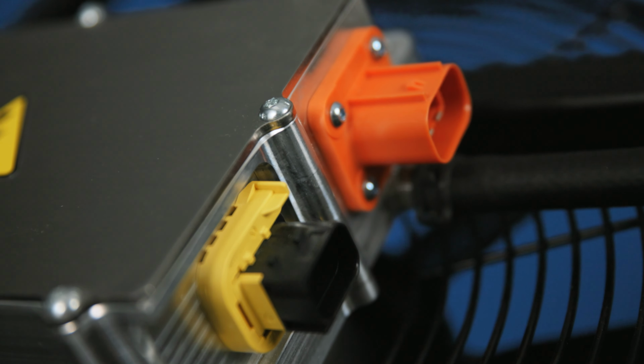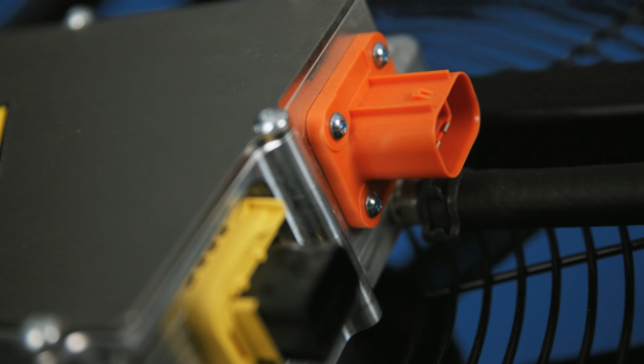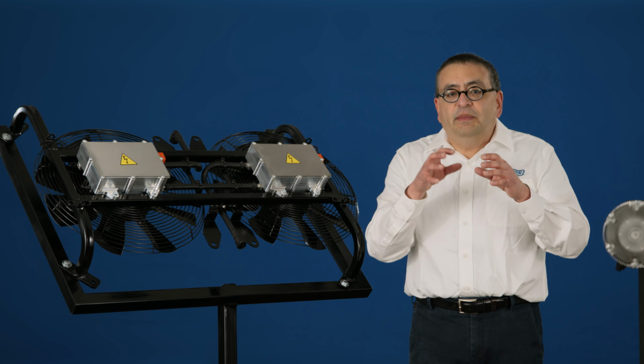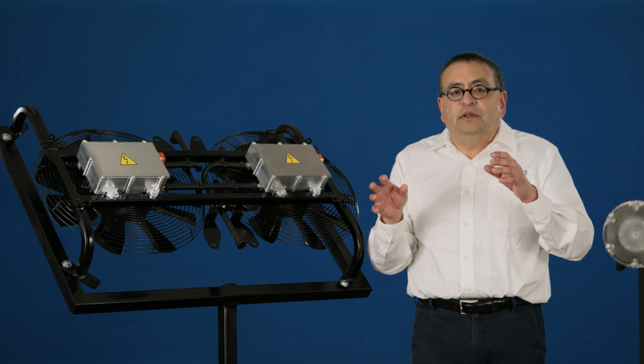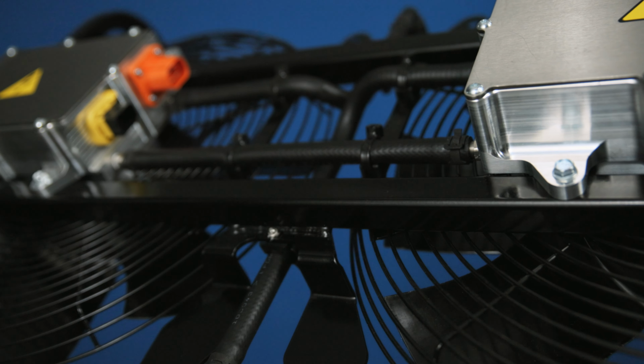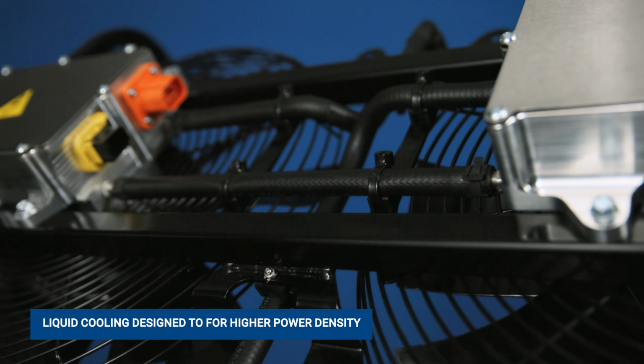Depending on the configuration or concept used by the OEM, it may take the form of several heat exchangers or one single heat exchanger with different regions that need to be cooled. A key difference will be the delta temperature we need to moderate between what's coming out of the radiator, the power electronics, and the thermal management of the batteries, versus the temperature coming out of the radiator and the diesel engine. The liquid cooling is applied due to the high power density of our system.